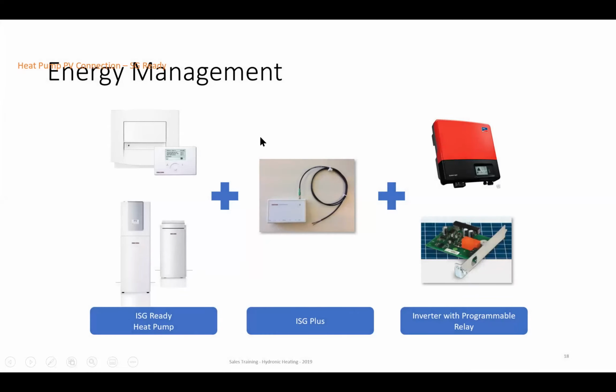Okay, this is the energy management slide, and what I'm going to describe is what we call our SG Ready function. So what SG Ready is: if somebody has a PV system, we want to take as much advantage of that PV generation as possible. So what we will do is take a direct signal from the solar inverter, with a programmable relay. That's important, so the solar inverter has to have some sort of brains in it itself. Most do, and there's greater levels of sophistication as well when it comes to some of the SMA product, which talks through the ISG to our product.